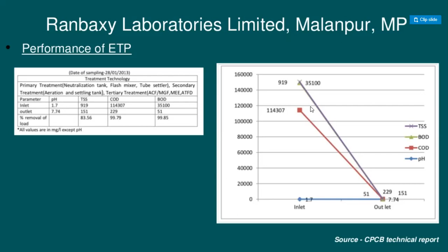Here COD inlet 1,14,307, but outlet 229. The percentage of removal of load is 99.79%, and the biological oxygen demand inlet is 35,100, but outlet is only 51. So almost 99.85% removal of load.